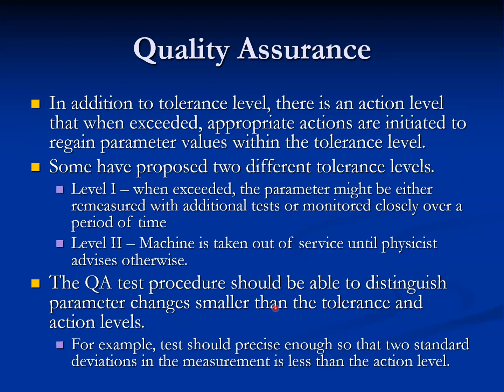Some have proposed two different tolerance levels: level one and level two. When level one is exceeded, the parameter might be remeasured with additional tests or monitored closely over a period of time. When level two is exceeded, the machine is taken out of service until the physicist advises otherwise. The QA test procedure should be able to distinguish parameter changes smaller than the tolerance and action level — for example, tests should be precise enough so that two standard deviations of the measurement is less than the action level.